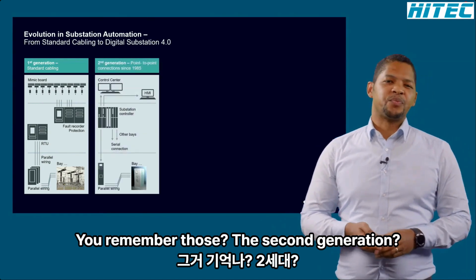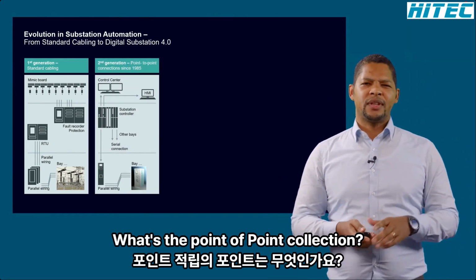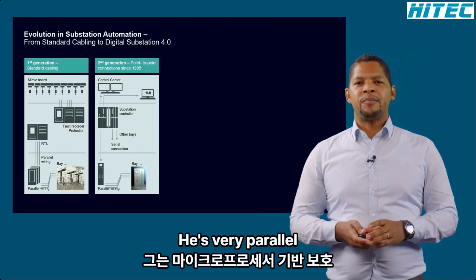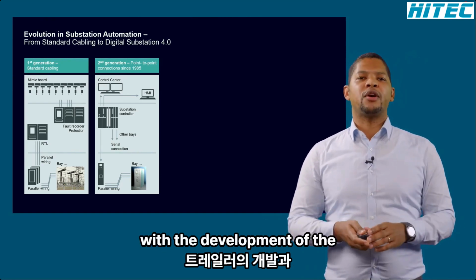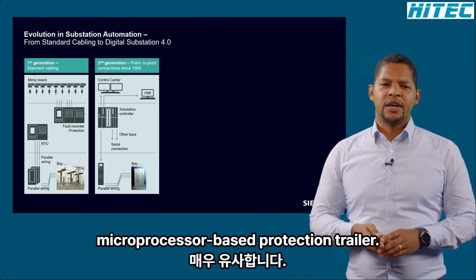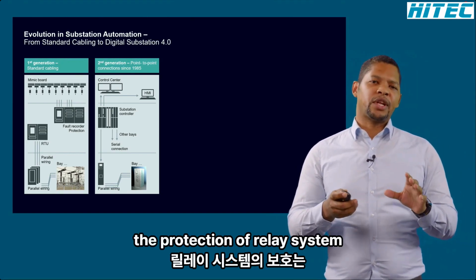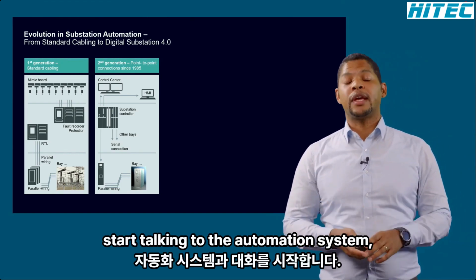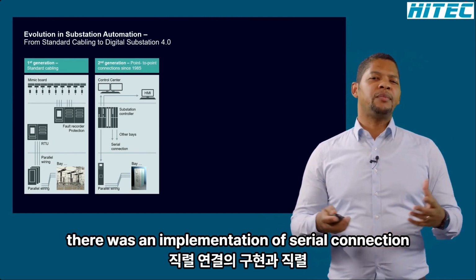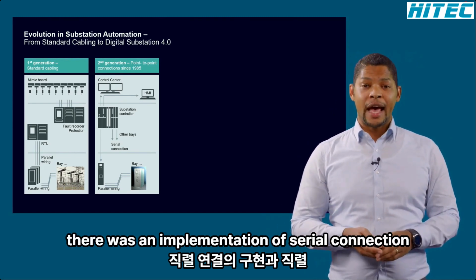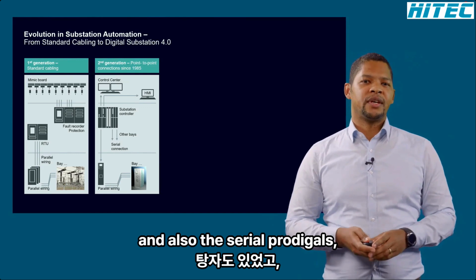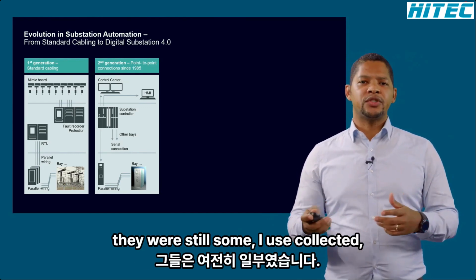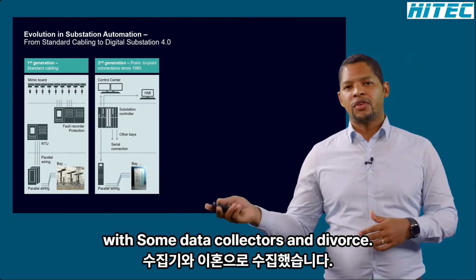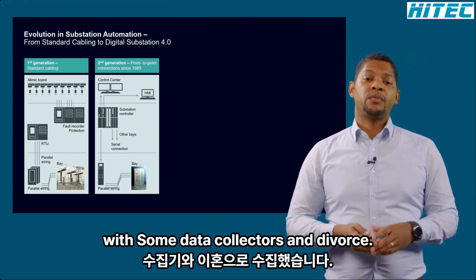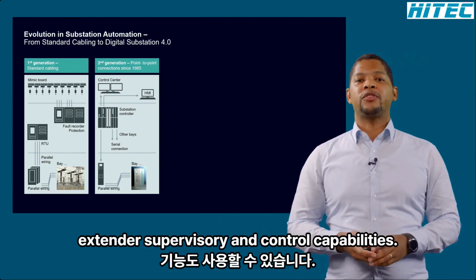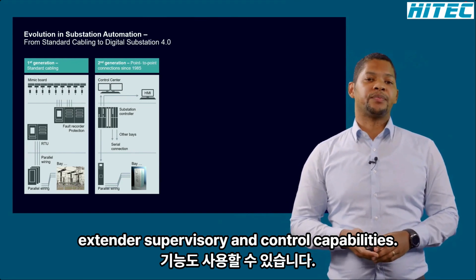The second generation was the point-to-point connection. That goes with the mid-80s, very parallel with the development of the microprocessor-based protection relays. So in this era, the protection relay system started talking to the automation system. There was the implementation of serial connection and also serial protocols. They were partially hardwired. There were still some IOs collected with some data collectors. And there were also extended supervisory and control capabilities available.